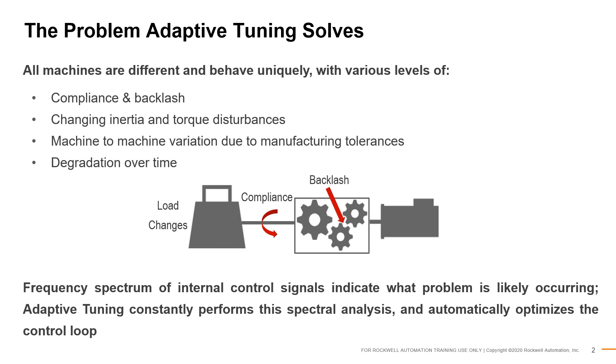With all the possible variations, the optimal tuning configuration can vary drastically across different loads, machines, and plants. Adaptive Tuning has been created to simplify the tuning process and to minimize the amount of effort required by the system configurator to get an application up and running. It works by continuously monitoring the frequency spectrum of internal control signals and automatically executes tuning actions to optimize the control loop.